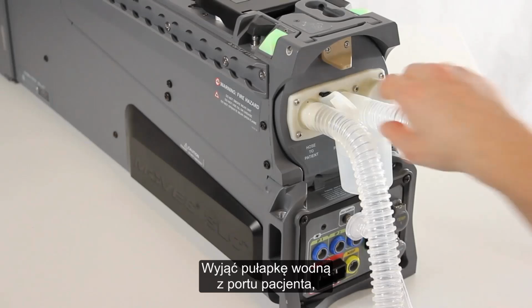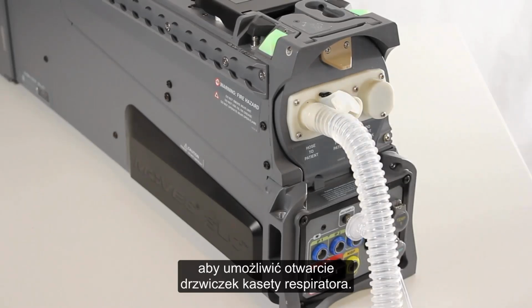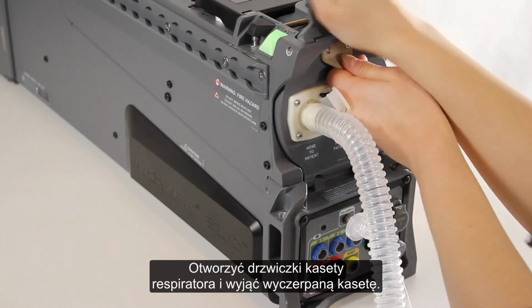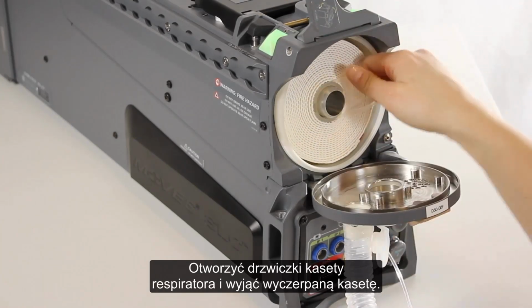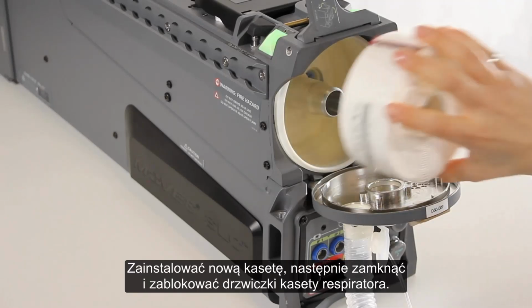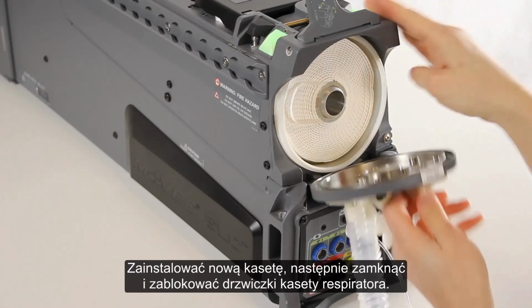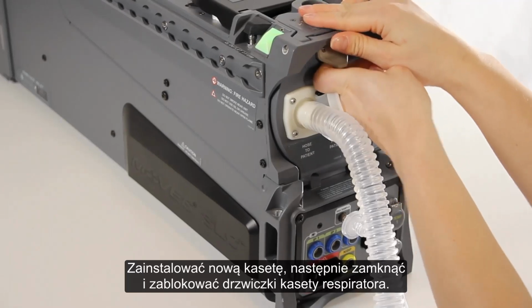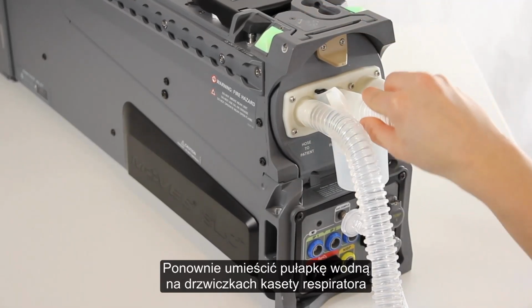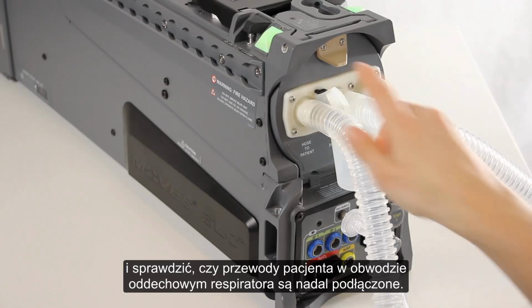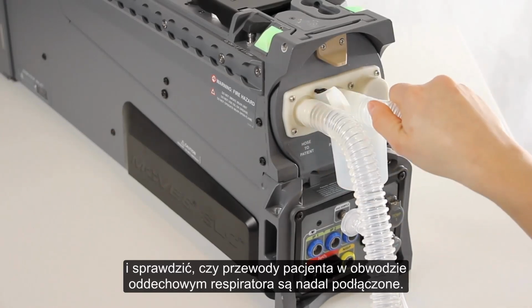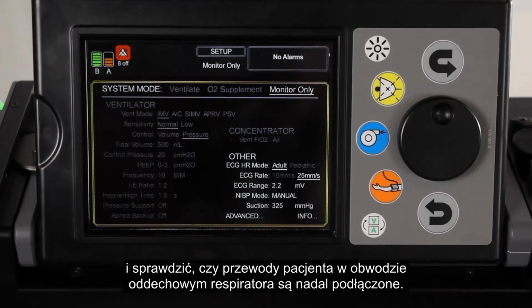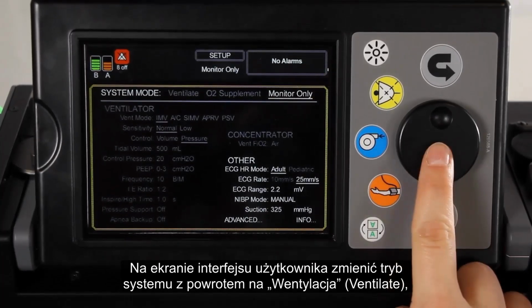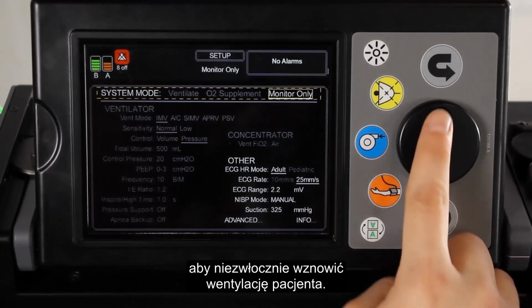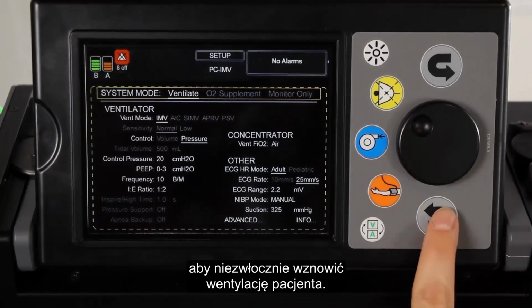Remove the water trap from the From Patient port to allow the ventilator cartridge door to open. Open the ventilator cartridge door and remove the depleted ventilator cartridge. Install the new ventilator cartridge, then close and lock the ventilator cartridge door. Reconnect the water trap to the ventilator cartridge door and ensure ventilator breathing circuit patient hoses remain connected. On the user interface screen, change the system mode back to ventilate to immediately resume patient ventilation.